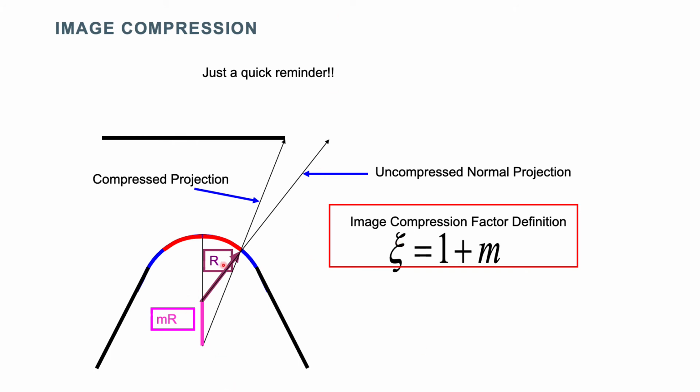So if we had no ion compression and the center of the projection was at the center of the spherical cap, we would have a radial projection like this. But actually, the quasi-stereographic projection means that the ions will be coming onto the detector here with some level of compression of the trajectories. So that's what the ICF means.